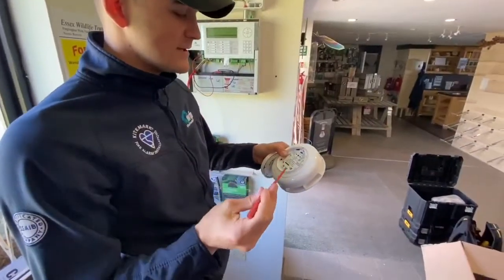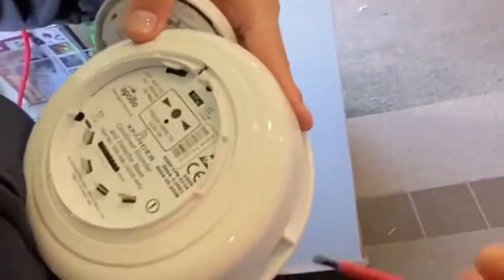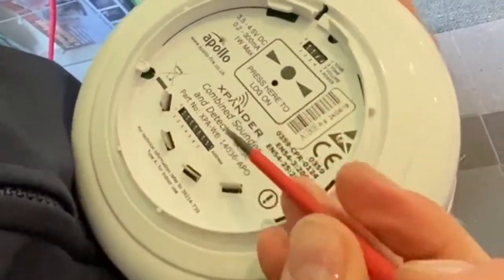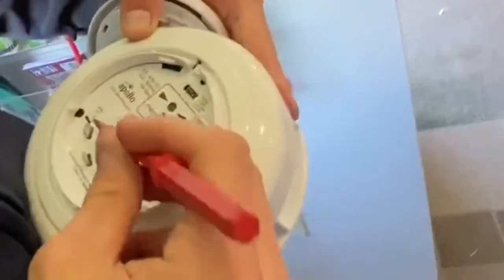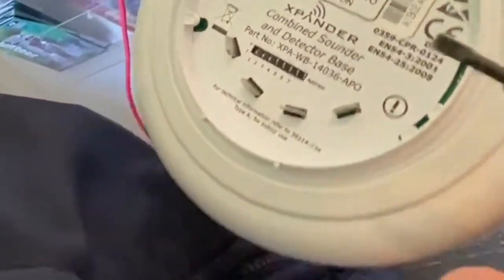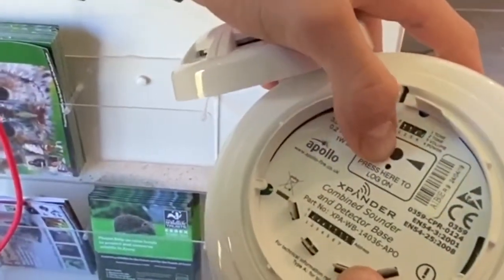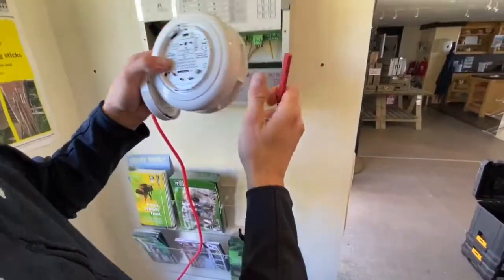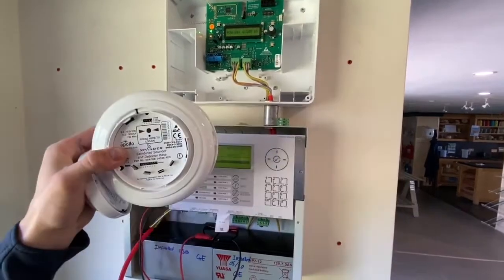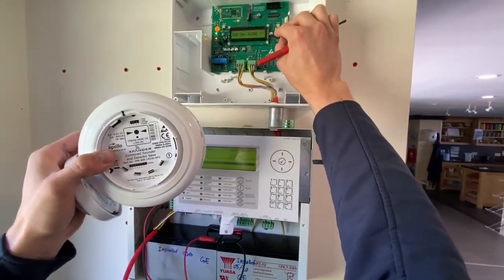You also have to do a learn on the sounder and the heat or smoke detector. First, power it on using the DIP switch - switch four down is for power. This one's going to be address seven, so switch one, two, and three on. Hold it down for three seconds to log on - the LED light will light up. Then go to the XPander, press the home button, select 'add new device,' and there it's found. Press yes to add it - that's the item number.